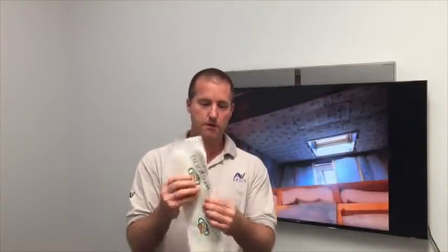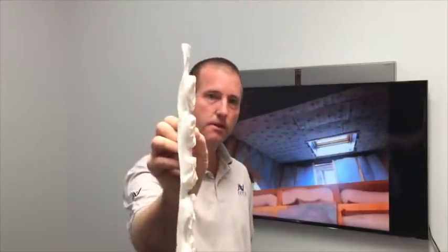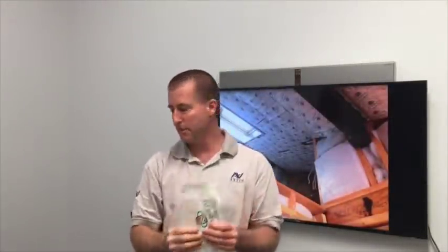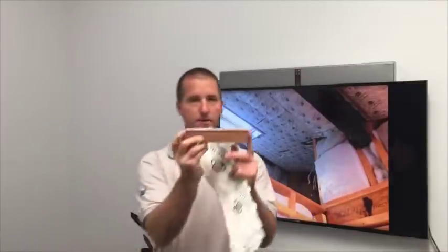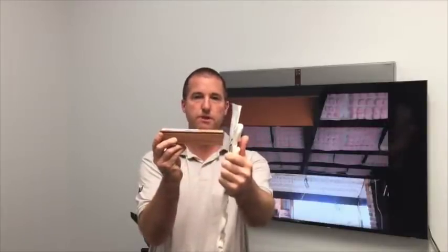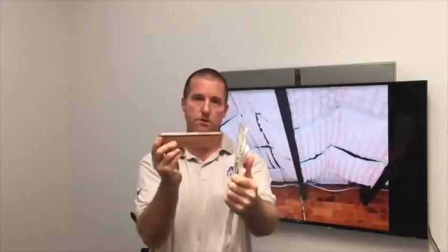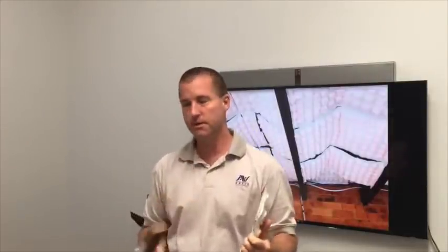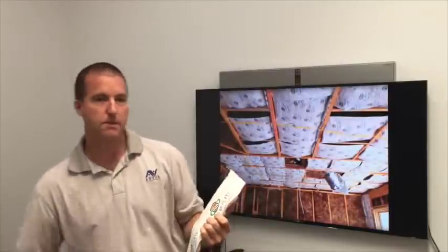In fact, this piece here, which is only about maybe 20 millimeters thick, generally speaking, simulates about 150 millimeters of brick, which is a brick about that thick. So you can imagine when you build a building, your actual internal volume of your building is much greater. If you were trying to use brick as an internal thermal mass versus phase change, you get a much bigger building on the inside for the same amount of material. It's much less expensive to build and it behaves itself. It doesn't overheat and doesn't underheat.